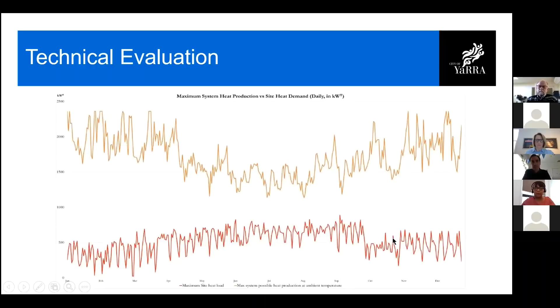For the graph, we plotted a daily average just to reduce the number of points, but it's based on hourly data. So you can see how the heating output from the system drops in winter, by about a third or so, but even at its lowest, we still had plenty to cover our peak demand. And honestly, although the system sizes were reasonable, I totally think we can even size down, especially if we improve the efficiency of the system using multiple heat sources.